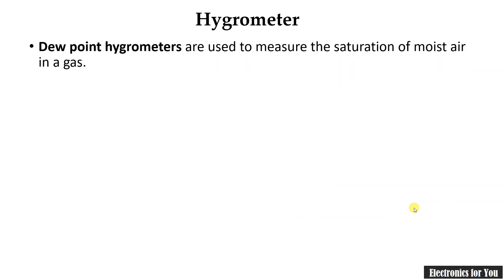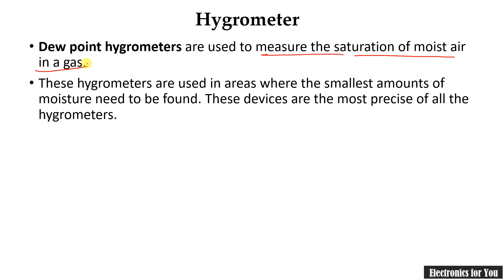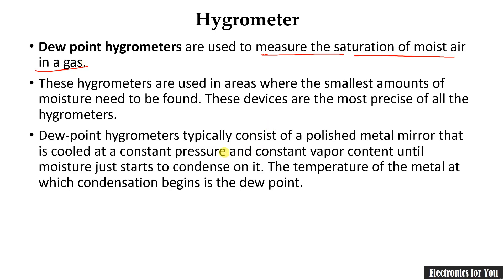The last type of hygrometer is the dew point hygrometer. It is used to measure the saturation of moist air and is one of the most precise types used in industry due to its very good accuracy. Dew point hygrometers typically consist of a polished metal mirror that is cooled at constant pressure and constant vapor content until moisture just starts to condense on it. The temperature of the metal at which condensation begins is the dew point.